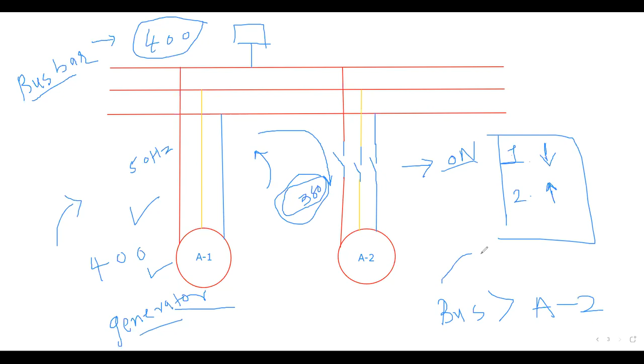So obviously this current, correct. You are going in the correct direction. There is a voltage difference between the bus bar voltage and the alternator voltage, and you can see that your bus bar voltage is greater than your alternator voltage. Current flows from high voltage to low voltage, so in that case it will go from your bus bar to the alternator. This is the phenomenon that will happen if you connect under this particular condition.